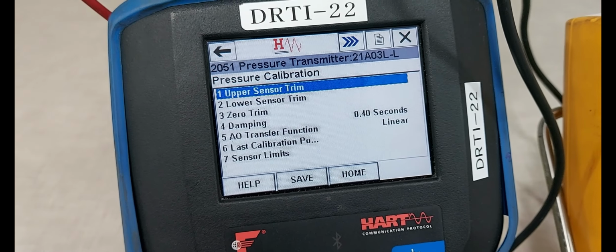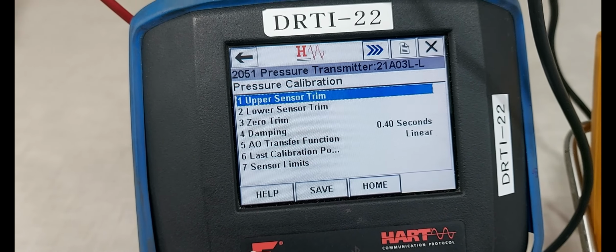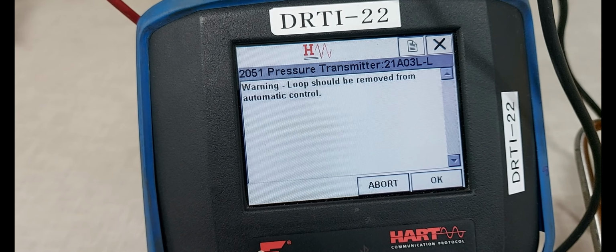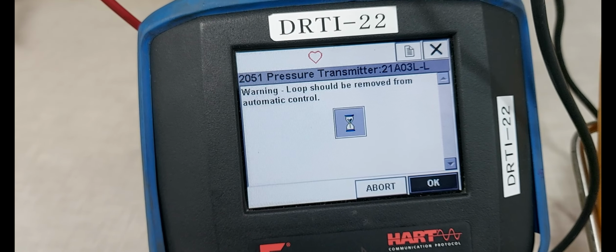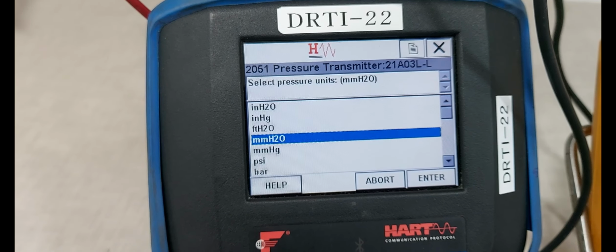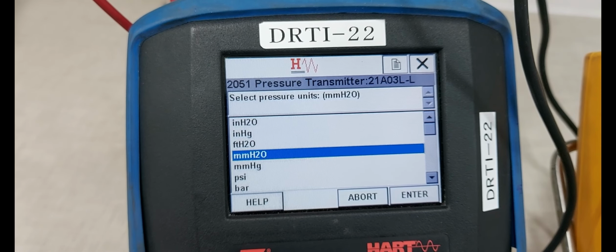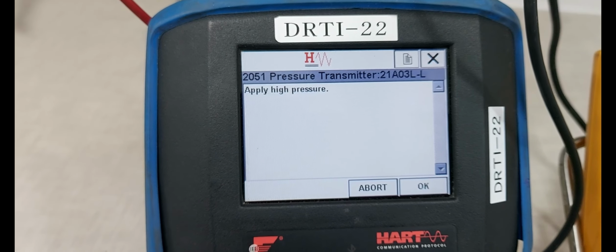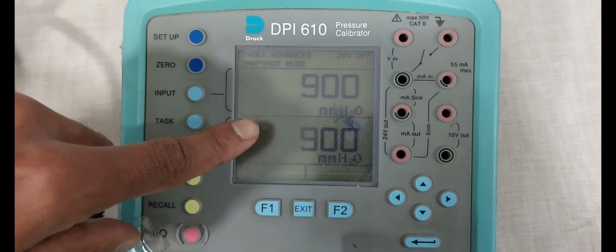Upper sensor trim. Select the upper sensor trim. Then press OK. Select the unit, mmH2O, enter. Apply the high pressure. Pressure already applied, high pressure. Then press OK. Pressure is stable now. Then press OK. Select the maximum value 900. Then press OK.